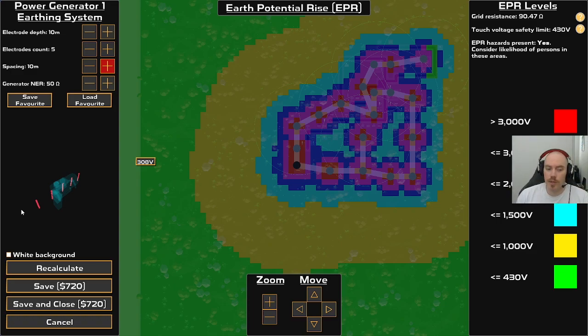That can be good because you want it to leave your asset, but it can also be bad. If there's a fault on this generator, any neighboring buildings will have a voltage of about 3,000 volts, which is quite a lot. That means if someone's walking or touching something, they'll get about 3,000 volts between two things they can reach with their arms, or between two legs if they're stepping at that distance.